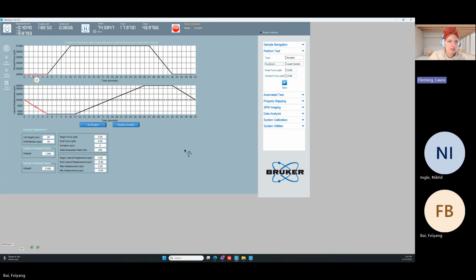We'll go segment by segment. So this first segment, this 0 to 5, my normal force is doing nothing, but I'm moving -5 in x. During this next segment, my x is doing nothing, but I'm loading into the sample. During this next segment, I'm loaded into the sample, but my normal force remains constant while I scratch. So then I move to the +10. Then we stay at that +10 while we unload to the sample surface. And then we come back to 0 in the lateral direction. So this is move backwards, load, scratch, unload, move back to 0. Pretty straightforward. Are there any questions about this one in particular?